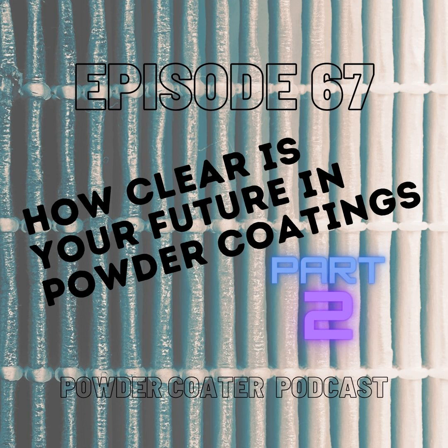Yes, that will save you money, but first of all, you could create a major safety problem for yourself if you shortcut purge. Purge is there for a reason. It's per code. Don't ever screw with it. Follow NFPA, your insurance company, everybody, you've got to do that. You can't put a VFD on a purge and turn it down and take shortcuts. It's just absolutely black and white. Don't ever do that.